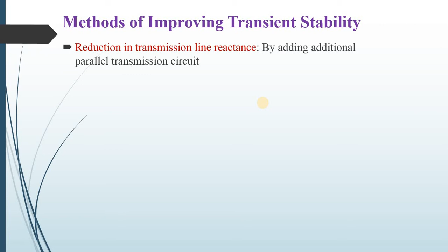So the first method is reduction in transmission line reactance. This can be achieved by adding additional parallel transmission circuits, providing series compensation on existing circuits, and by using transformers with lower reactances. So to reduce the transmission line reactance, we can add an additional parallel transmission line.